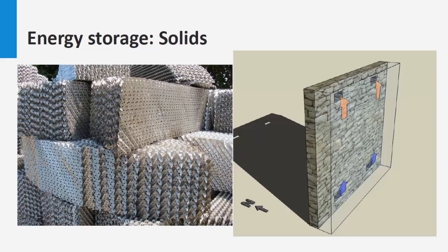In the operation, the flow is maintained through the bed in one direction during the addition of heat and in the opposite direction during removal. A packed bed in a solar heating system does not normally operate with a constant inlet temperature. During the day, the variable solar radiation, ambient temperature, collector inlet temperature, load requirements, and other time dependent conditions result in a variable collector outlet temperature.